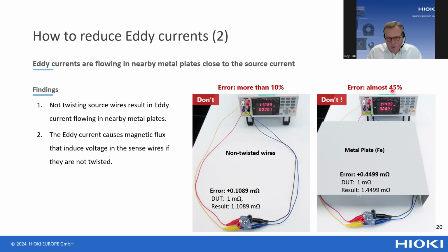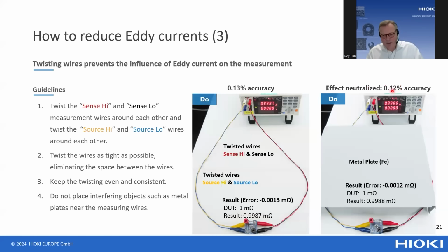So what can we do about it? Once again, the solution is twisting the wires, both the sense wires and the source wires. Without the metal plate, the measurement error is 0.13%, and even with the metal plate nearby, the result is not influenced. So twisting the wires is a very efficient way of cancelling out the effects of eddy current.